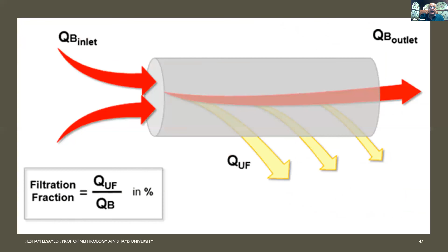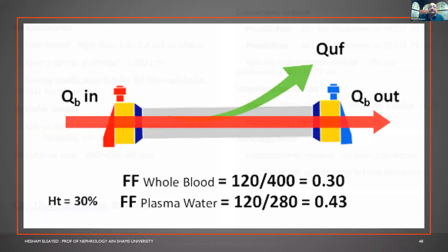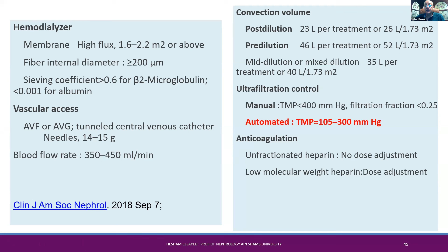So filtration fraction is important, and it depends on the UF and the Qb. If you are increasing the filtration fraction, the filtration will stop due to very high protein content and hematocrit. So the key is to increase the blood flow. And this is the final point: the hemodialyzer surface area and sieving coefficient should be very high. Using a good vascular access is better. If you need to go with very high blood flow, you need special needles of 14 or 15 gauge. The post-dilution volume is around 23 liters, and the pre-dilution is around 50.